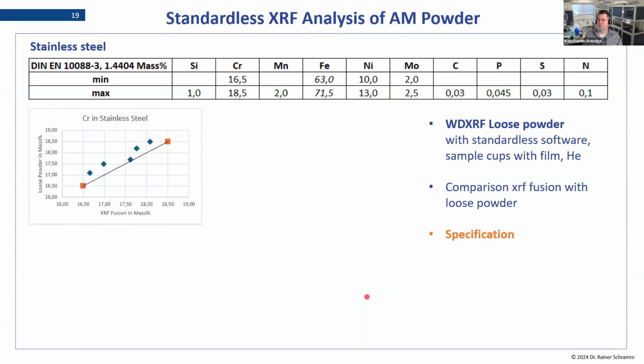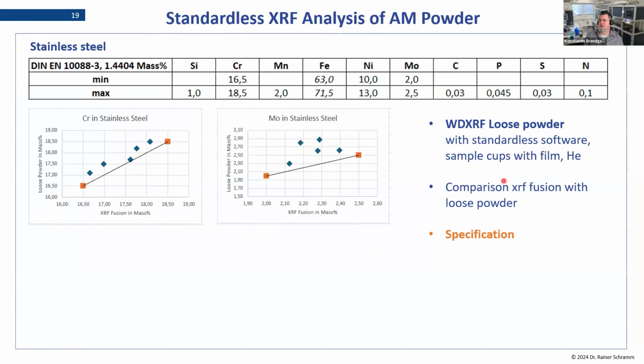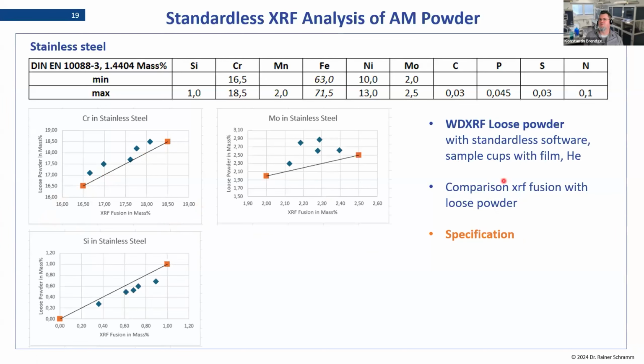What we did was compare our loose powder method, done on a standardless software, in this case a wavelength dispersive unit. So it was the same equipment that we used for the XRF fusion method. And we compared the specification versus the two analysis techniques. As you can see from the graphics, they are both very promising because they're inside the specification.